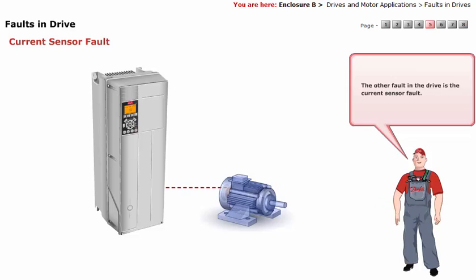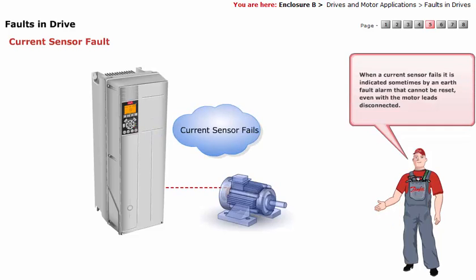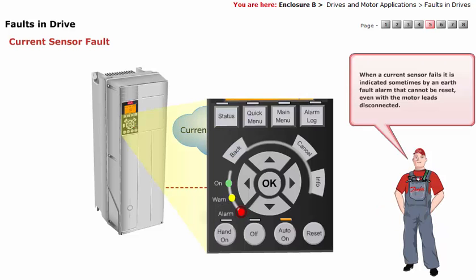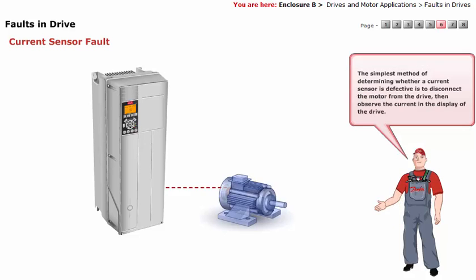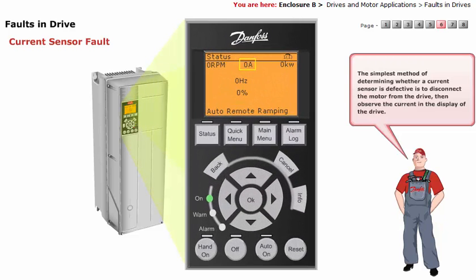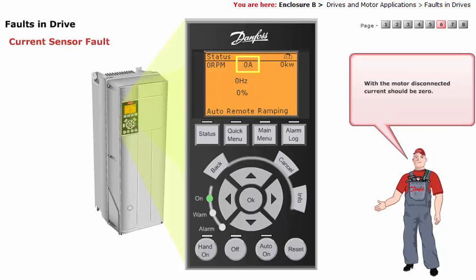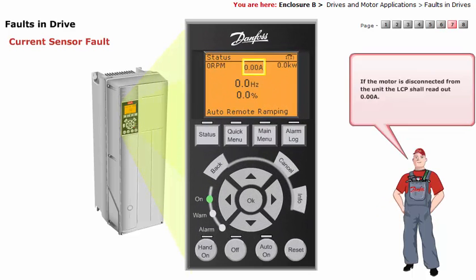The other fault in the drive is the current sensor fault. When a current sensor fails, it is indicated sometimes by an earth fault alarm that cannot be reset, even with the motor leads disconnected. The simplest method of determining whether a current sensor is defective is to disconnect the motor from the drive, then observe the current in the display of the drive. With the motor disconnected, current should be zero. If the motor is disconnected from the unit, the LCP shall read out 0.00. If anything else is shown, this indicates a defective current sensor.